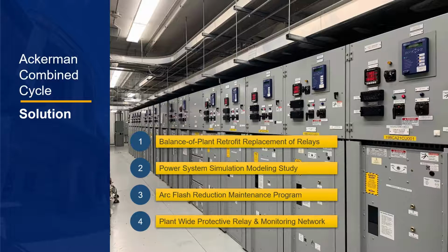The design effort started with a full electrical power system analysis using the software program ETAP. The study provided a protective device setting coordination reset and confirmed the method of integrating an arc flash reduction program with the use of maintenance mode switches. The recommendation of adding a new plant-wide protective relay network supplied a means of improving system monitoring as well as supplementing the asset management initiative.